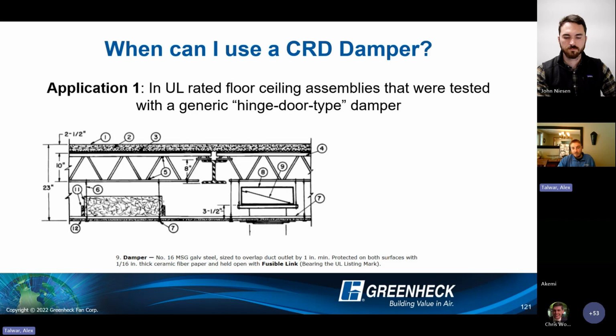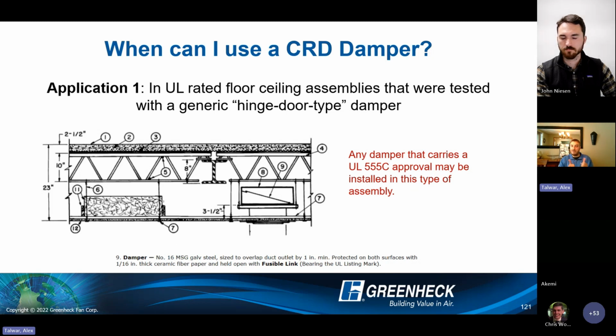Type application 1 here. If you see a design like this, we scroll down, we look at number 9, we see damper. Oh, we got a damper listed in here. That means we can put a damper in this type of construction. If we read a little more, there's nothing too specific about that damper, right? It's basically just describing a hinged door style damper, something that's held open that's going to close when the heat increases. So if you see something like this, where there's a generic description of a damper, any UL 555C classified product may be used in this type of a design.